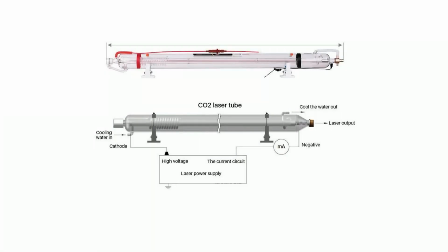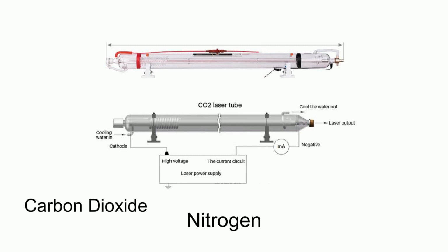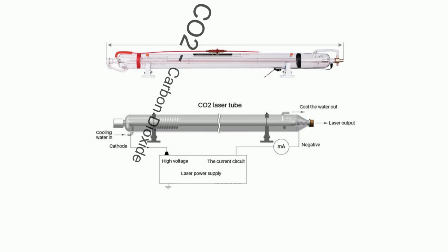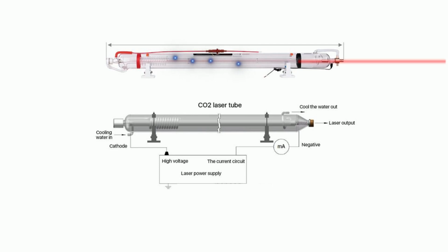Without getting technical, we produce the laser beam with that glass tube that's at the back of the machine. The glass tube is filled with gas. The gas is mainly carbon dioxide, nitrogen and helium, CO2 being the reason we call it the CO2 laser. We pass electricity through that gas and it excites it, and that just means it gains energy, and the production of that is light or photons. So the more energy we put in, or the more power, the more intense the light that we're going to emit, or the laser beam that we have as a result.